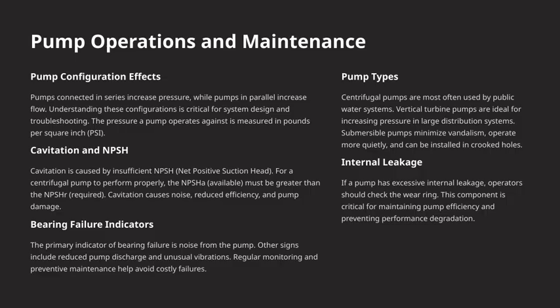Next, let's consider cavitation and NPSH. Cavitation happens when there's not enough net positive suction head, or NPSH, available at the pump inlet. Specifically, the NPSH available must be greater than the NPSHR, the required head, for the pump to operate properly. If cavitation occurs, it can cause noise, reduce efficiency, and even damage the pump, so it's something we want to prevent through proper system design and maintenance.